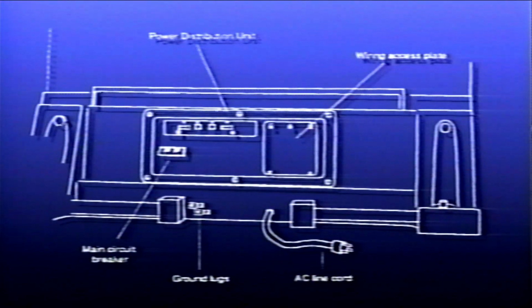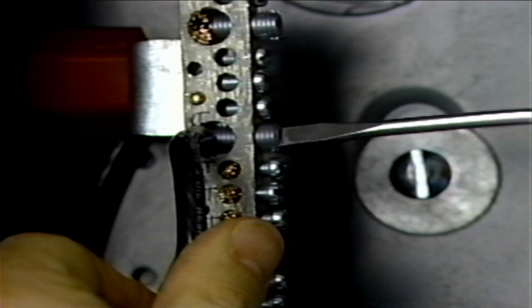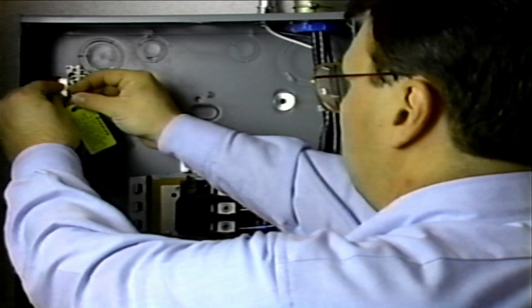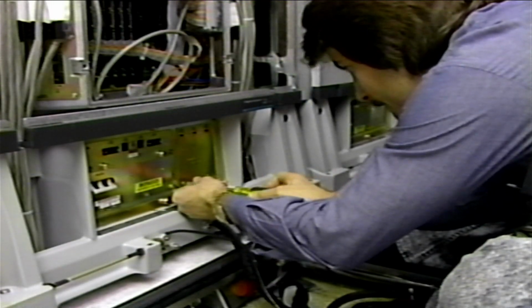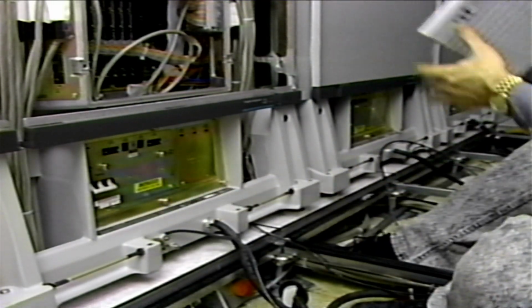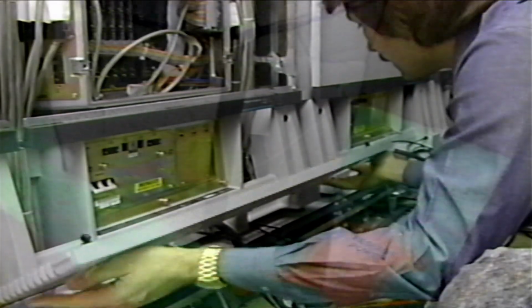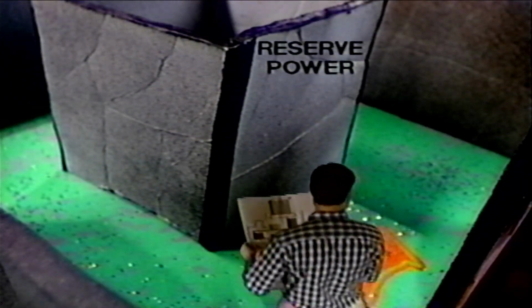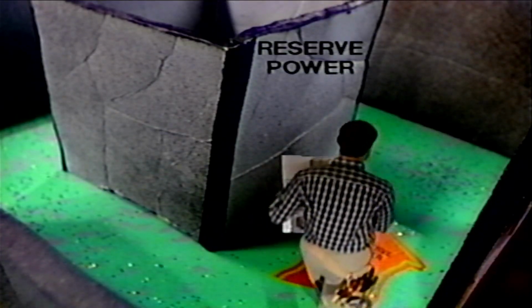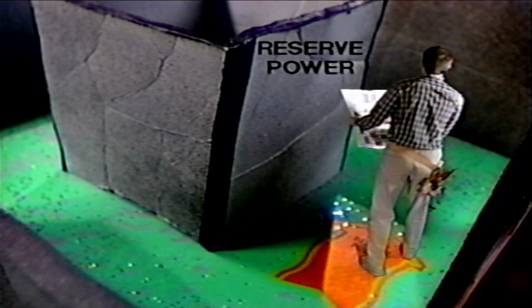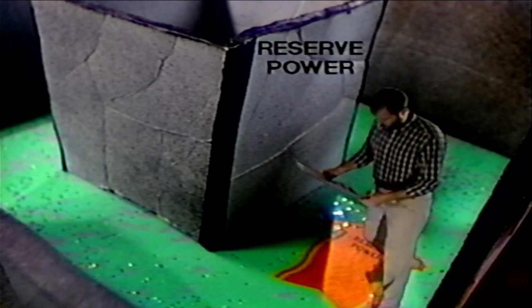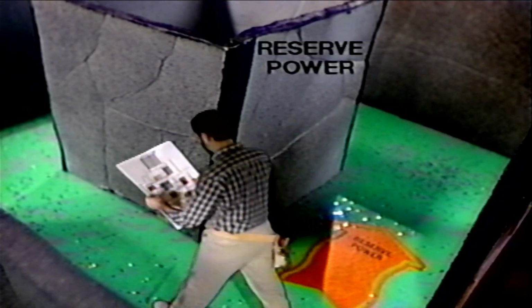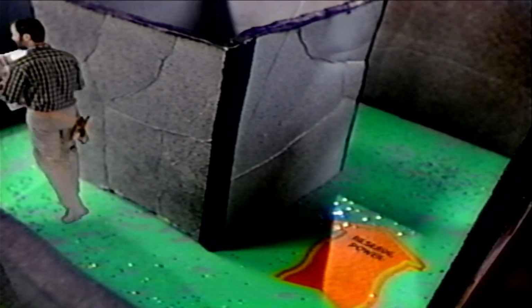Install the system ground between the terminal board connector and the AC panel ground bus bar. Be sure to tag the ground in the AC panel with a warning label. Then, replace both the wiring access plate and the rear pedestal cover on each column. At this point in the installation, you can install a reserve power supply if the plans call for it. However, if you need to connect the Meridian1 to an uninterruptible power source, be sure to follow the manufacturer's instructions.